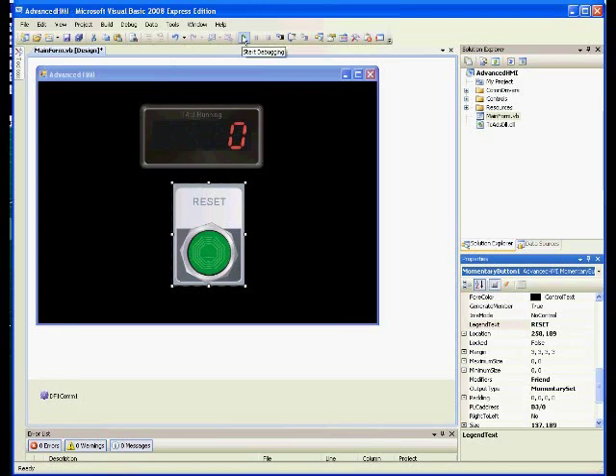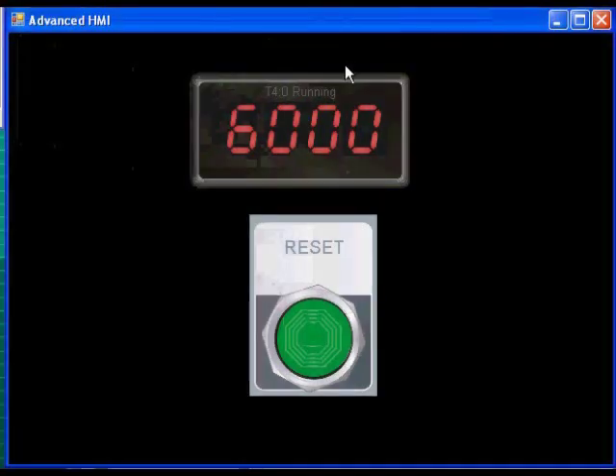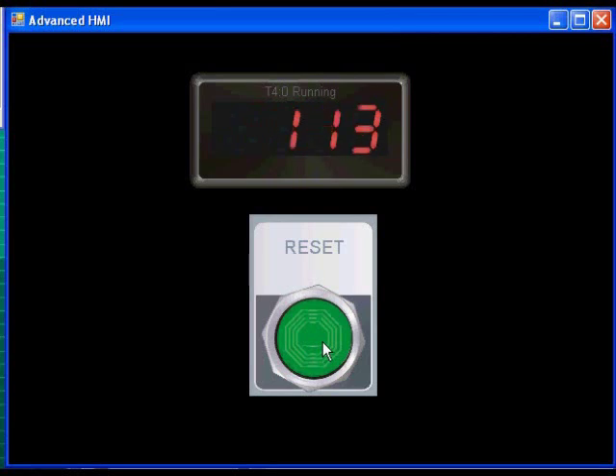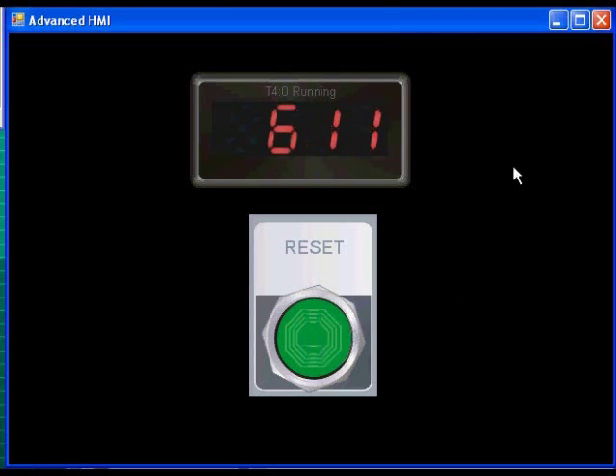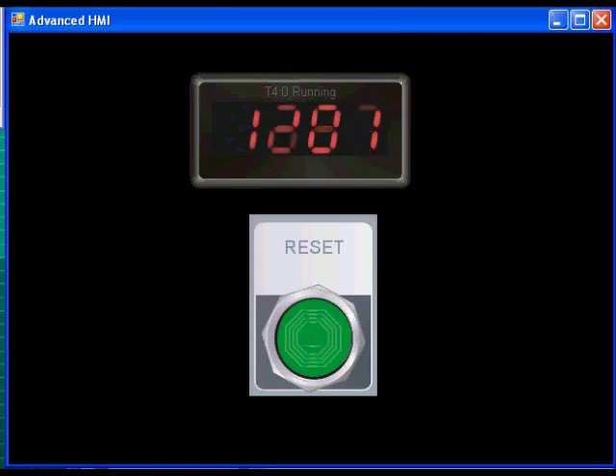Once that's done, let's go up to the VCR play button and run the application. Once the application has started, if you're connected to the PLC and have power, it will search for and find the baud rate settings, then begin reading the values out of the PLC. You'll be able to see your accumulation value of your timer, and when you hit the reset button it will reset. There we have it, we've built our HMI.